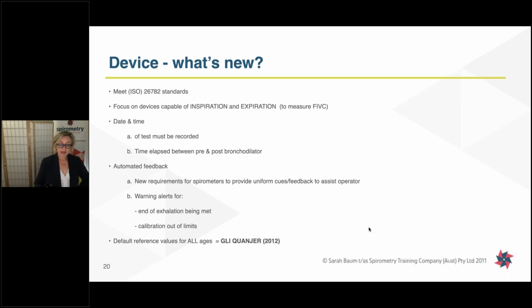They cover a few more issues in detail about the device. What's new regarding your spirometer is that all spirometers now must meet the ISO standard 26782. So if you're in the market for a new device, always make sure it meets that standard. They now focus on devices that are capable of inspiration and expiration. The reason for that is there's a heavy focus now on measuring a breath in at the end of the test. So after complete exhalation of spirometry, we now introduce an inhalation, just as rapid and just as full at the end of test, and we call that the FIVC.